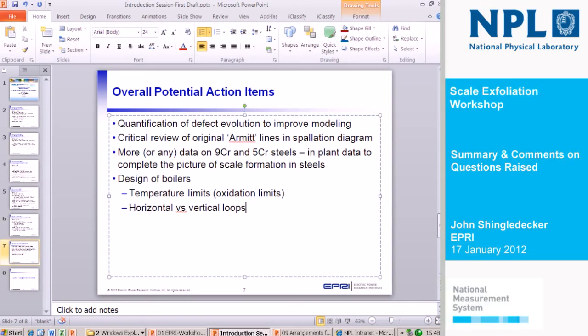Yeah. Barry, I was going to say I was surprised by the same thing. Most everything that we've seen in EPRI has always been in the loops, collecting in the loops. And the horizontal ones still have problems with erosion and other things, but they don't have problems with exfoliation. We actually had it in my boiler tube book, build a horizontal surface, because essentially there has not been, as far as I know, anywhere in North America that's had a problem with horizontal surface. And every unit in Canada is horizontal. But our horizontal designs are a little different.